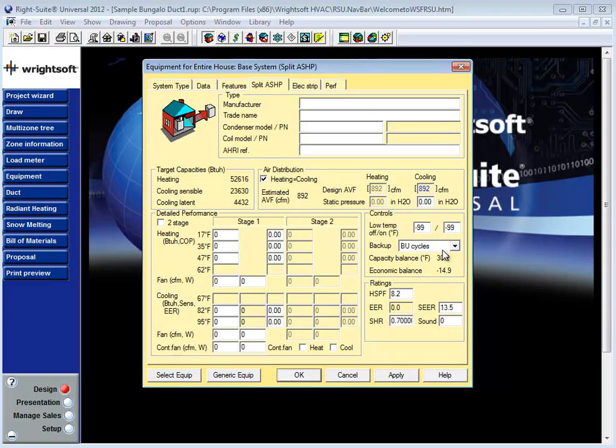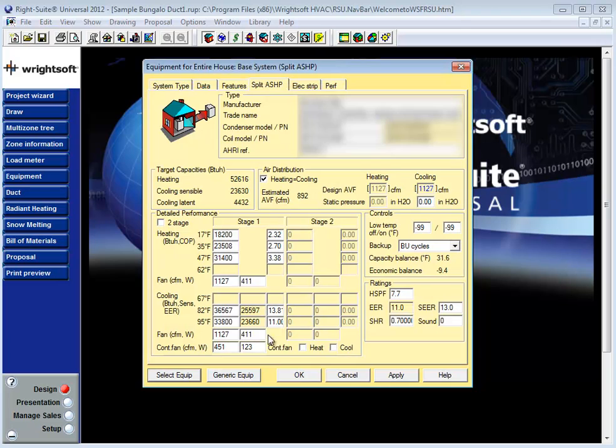If I choose not to select a piece of equipment using manual S data, if I simply hit the select equip button in the bottom left hand corner find the equipment that I want to select and click OK the equipment data used is all based on AHRI data which doesn't necessarily tell you the needed CFM to create the ideal operating conditions of that equipment.